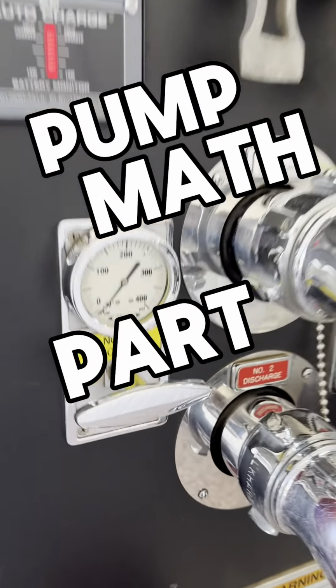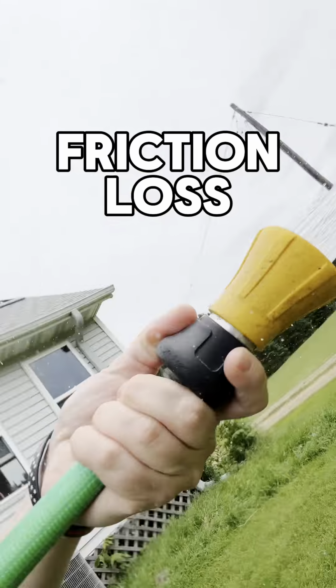Pump math part 3. Friction loss. Let's say this nozzle wants 30 psi to operate properly. Yeah, I'm making that up. To get 30 psi there, I start here at 40 because I lose 10 psi as all that water travels through the hose. We all know it costs energy to travel.